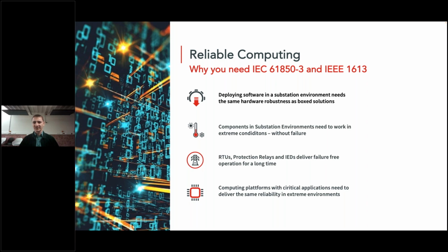We heard a lot about software that is running now in substations instead of boxes like IEDs. So if we run software, we need to make sure that the software is running on very reliable hardware as well, because we need to meet the reliability that we are aware of from RTUs, protection relays, IEDs, but also firewalls and other equipment. So if we deploy software, we need to make sure that we deploy it on the same hardware specification as the box solutions in terms of robustness. The reason behind this is that substations are usually unmanned. They're operated in harsh environments. We have a very high EMC level. They need to operate at any time without failure.